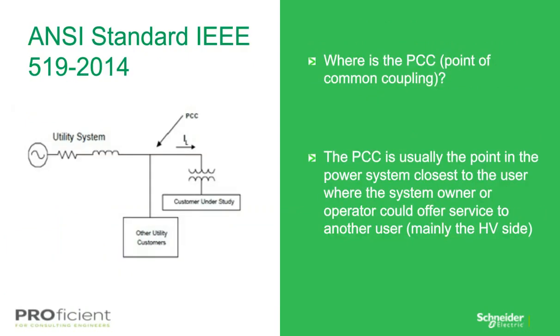Okay, so next we'll get into the point of common coupling and some of the definitions there. The interface between the consumer and the utility is basically the closest point on the utility side of the customer service where another utility customer is or could be supplied. The ownership of any apparatus, such as a transformer that the utility might provide in the customer system, is immaterial to the definition of PCC.